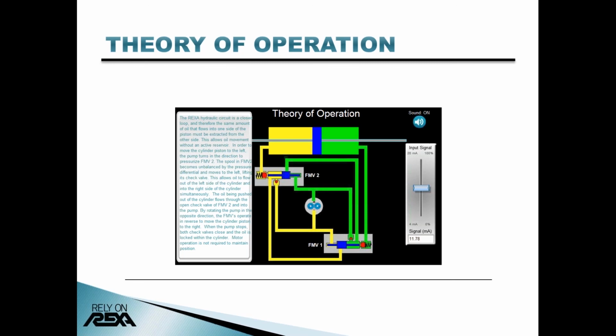A small Rexa system, something that would require a smaller cylinder for lower thrust output and shorter stroke length, something like a desuperheater spray valve application, may only have a total of 8 to 10 ounces of oil in the entire hydraulic circuit, including cylinder. A larger Rexa circuit, one with higher thrust or output and longer stroke requirements, like one driving a governor control valve rack, may have as much as 2 to 3 gallons of oil total in the system. But this is a far cry from typical power plant control oil systems, which could have 500 to 1,000 gallons of oil in the entire system.